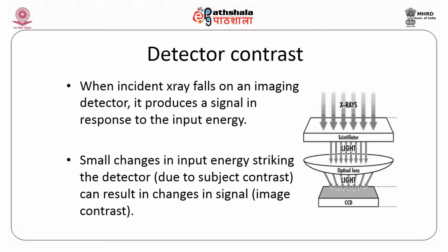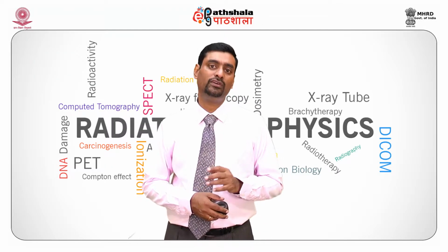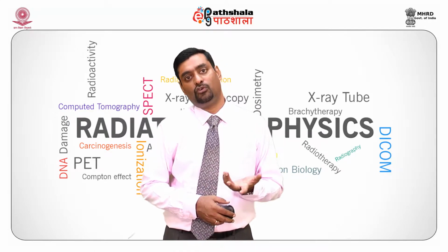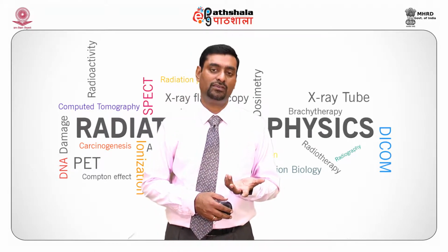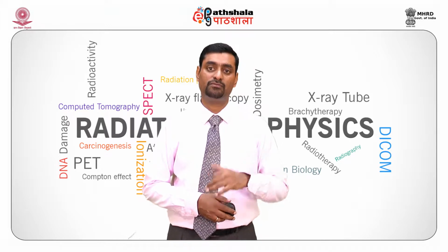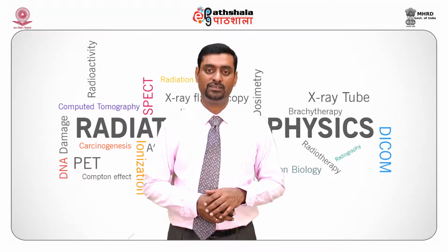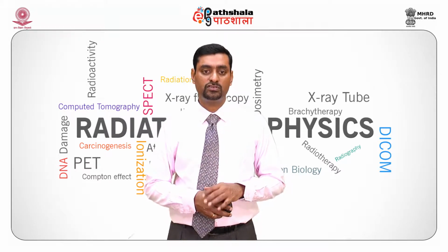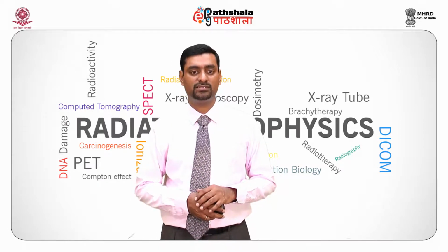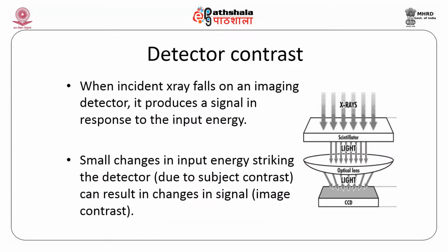It may be a very small X-ray input, how the detector is going to behave, or a very high X-ray input, how the detector is going to give the signal. Low intensity X-rays obviously give you a low amount of light or signal, but high intensity X-rays of course give a bigger amount of light, so better image quality. So small changes in input energy striking the detector due to subject contrast can result in changes in the signal, which is nothing but the image contrast.